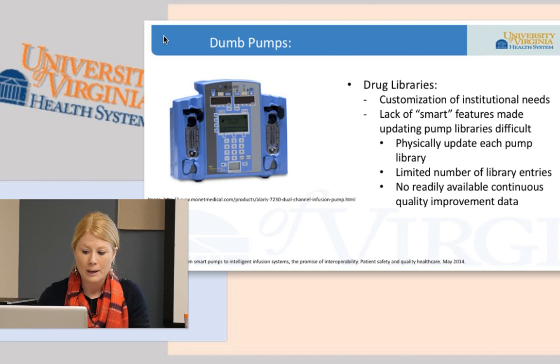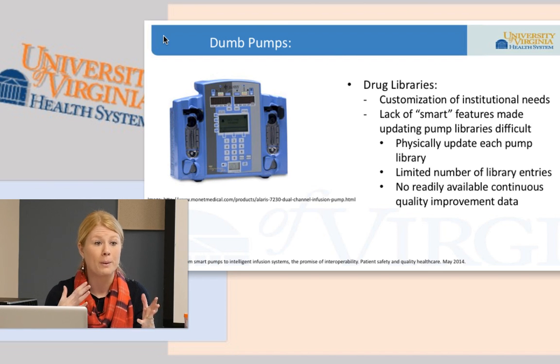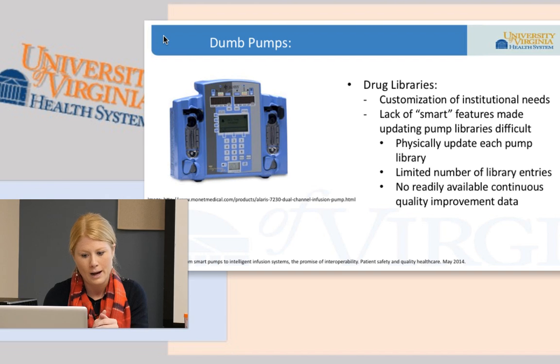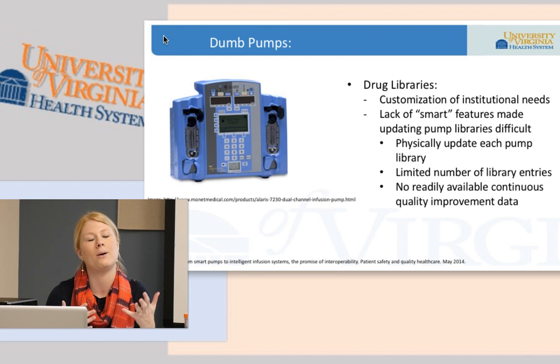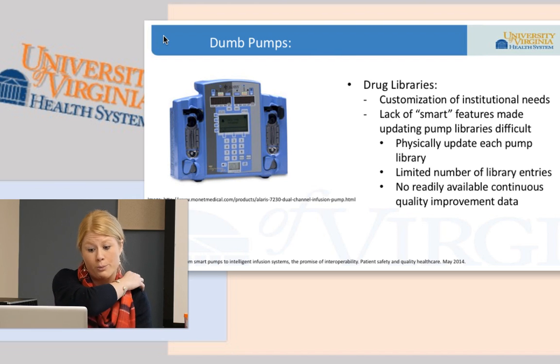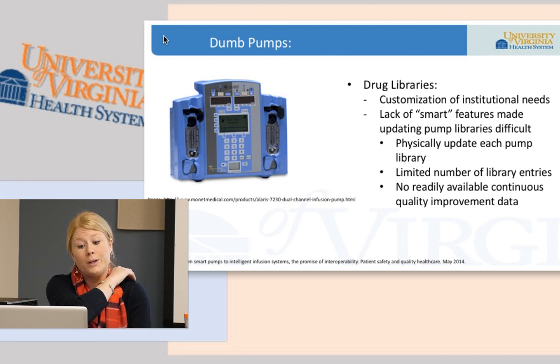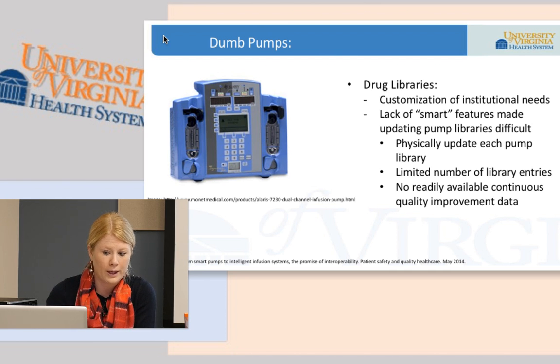And we'll talk a little bit more about why this would be important, but there really was no readily available continuous quality improvement data. So in order to get any information off the pump, if there was a question of was this infused properly, or was there something that happened from the pump, you had to go physically touch the pump, and of course with perishable information that would be something that would be a timely manner and would require somebody to actually go to the patient's room and get the pump. And then you would not be able to use that pump on another patient while you were reviewing it. So it was a problem of resources and limitations of the pump itself.